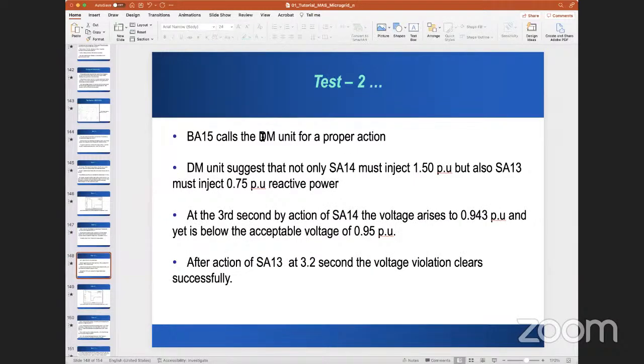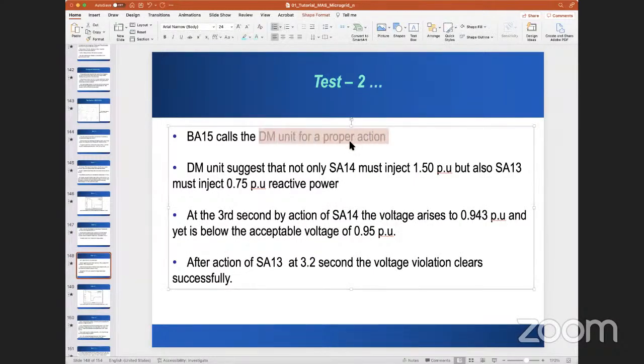Now BA15 calls the decision-making unit for a proper action. The decision-making unit suggests that we need STATCOM 14 and STATCOM 13, and both should inject this much power, 1.5 and 0.75. So at the third second, by the action of SA14, the voltage rises to 0.943, which is not enough, and is still below the acceptable 0.95. Then at 3.2 seconds, the STATCOM at 13 removes the violation because it is injecting 0.75 additional reactive power into the system.